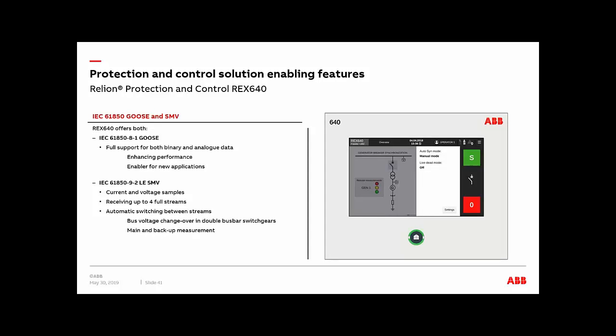So when it comes to IEC 61850 GOOSE and sampled measured values, you can have full support for both binary and analog data. The relay is going to give you the possibility of having the streams that we mentioned before, 4 full streams, current and voltage sample values. And you can have automatic switching between streams. So you can have a main and a backup measurement as well. If you're using it specifically for protection, this is going to be important.